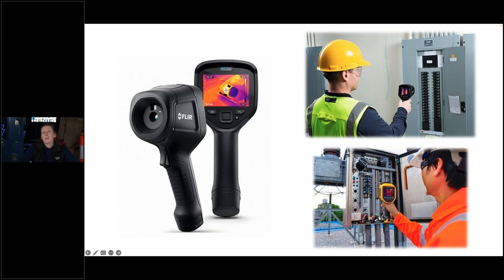You should definitely be wearing your PPE if you're going to open up and expose that. There should be boundaries in place, all the wonderful things. I'm just going to assume the one on the bottom didn't have it on while they opened it up, because that'll make my heart a little bit happier as far as safety is concerned, but then it doesn't make the infrared scan very useful. So it does require someone qualified, because they're going to have to open it up and expose those conductors and circuit parts. You have to know what the hazards are, and be able to address them appropriately with PPE and boundaries before you can do an infrared inspection. Just a little side note there.